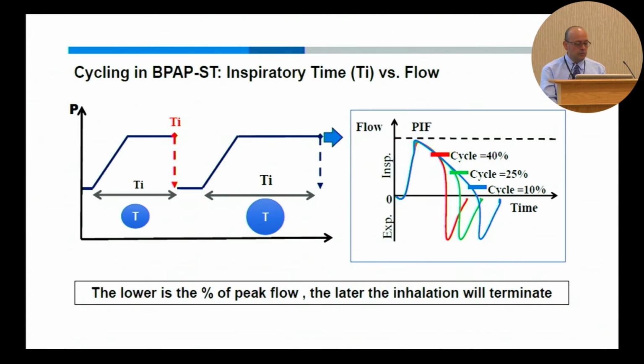This is what we were talking about before with the Respironics device. So you see this is inspiratory time. So you set the inspiratory time. Let's say this is 1 second. Once you reach 1 second, then the device automatically goes to expiration. If you are with the Respironics device and the patient takes their own breath, now it's going to cycle by flow. And this is what I was talking about before. The flow is effort dependent. And it also depends on which disease, how you can set up this flow.